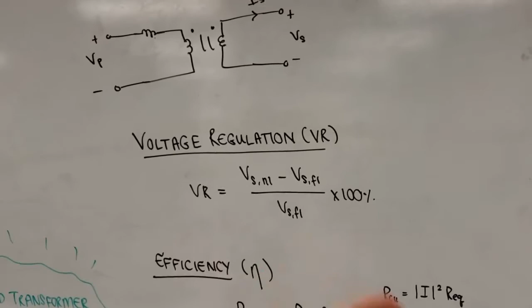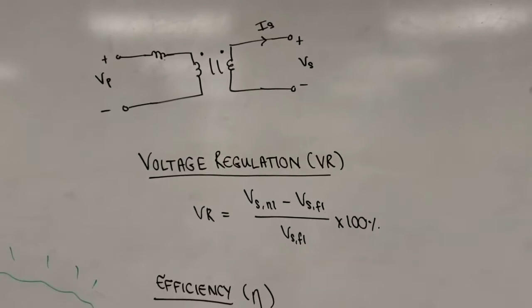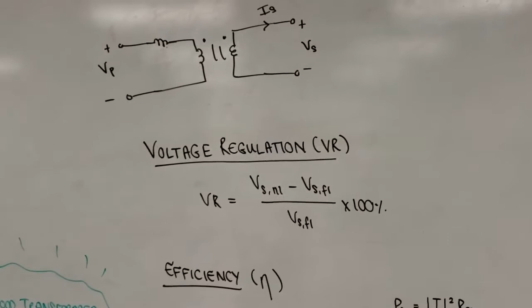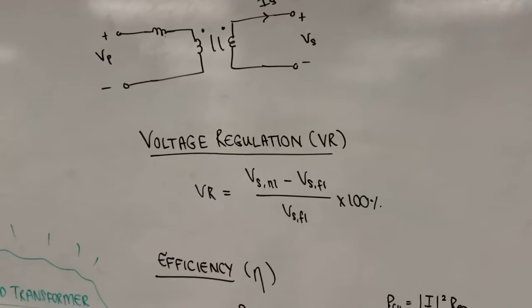Then if you converted those values to per unit, you'll find that if they fall in these ranges, you have a good transformer. If your R equivalent is 0.01 per unit and so on, going down the list, then you have yourself a good transformer. If you forgot how to do per unit, here's a real quick rundown.